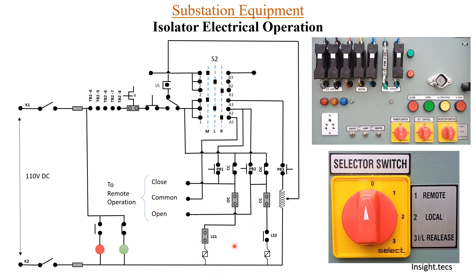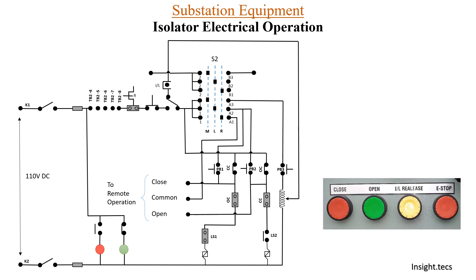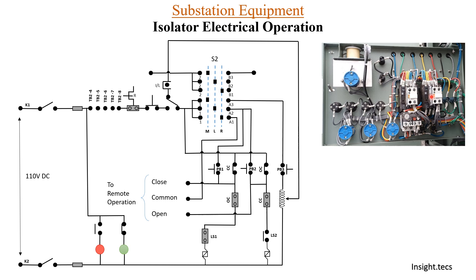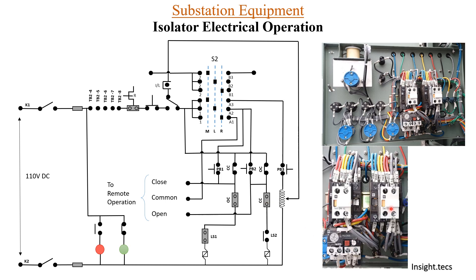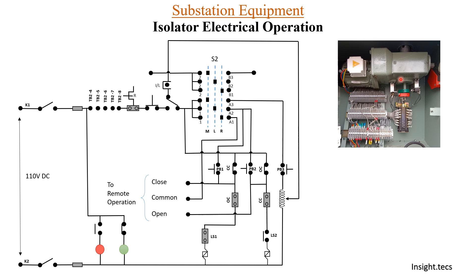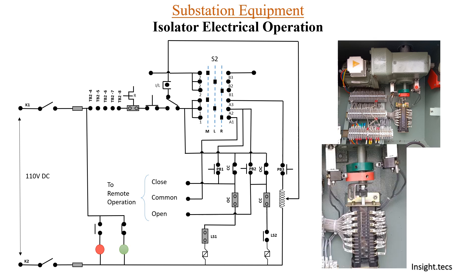Power then moves to LS1. CC and OC contactors each provide one NC contact in the circuit. When the motor starts rotating to close the isolator, once the isolator is completely closed, a limit switch (LS1) is pressed — this indicates the isolator is completely closed. Once the switch is released, the contactor opens and the motor stops rotating.